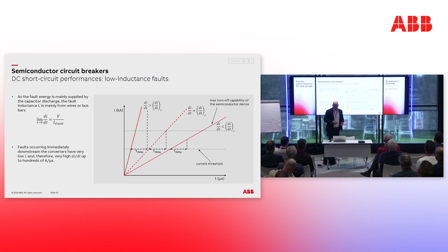And this also brings me to my next point. Solid-state circuit breakers are for sure not replacing electromechanical circuit breakers. They enable us to design new systems, but we are not going to design a DC system where everywhere there will be a solid-state circuit breaker, or at least not in the near future. So what's the main difference between the two? While in an electromechanical breaker, we have a limitation on the short circuit capacity, the amount of short circuit current we can pass and the amount of short circuit current that we can open, with solid-state circuit breakers, you pretty much don't have this, because depending on your threshold, your maximum let-through current is defined, given by the di/dt that we discussed, and will always be the same at this critical value.